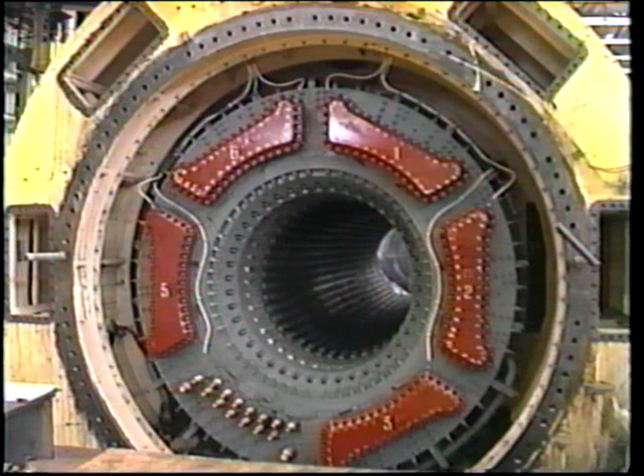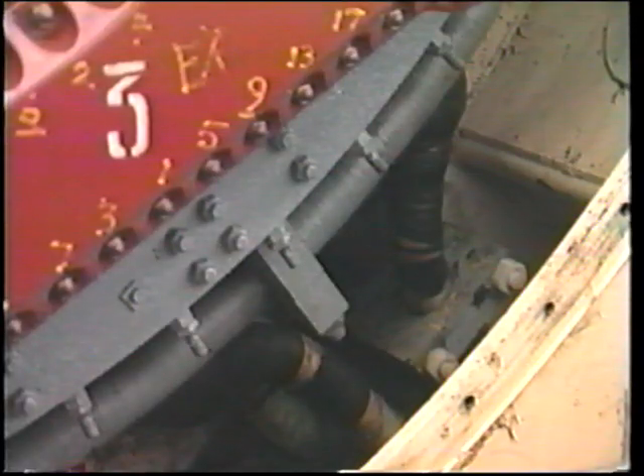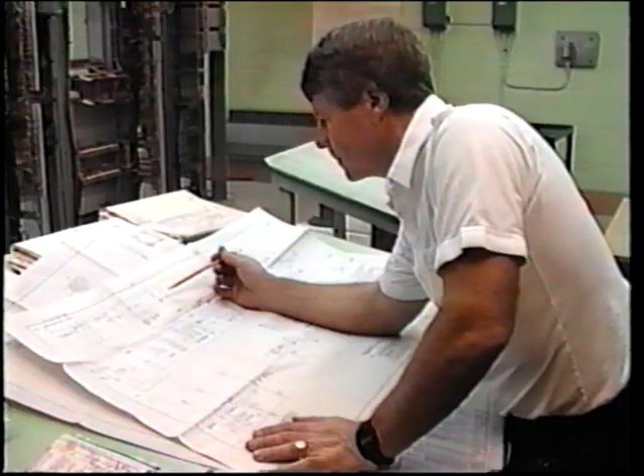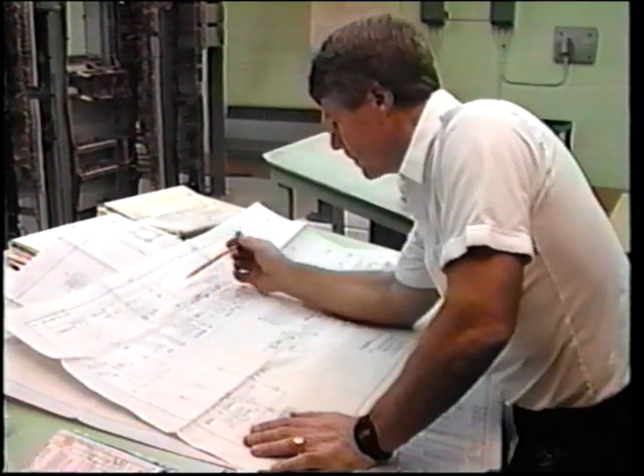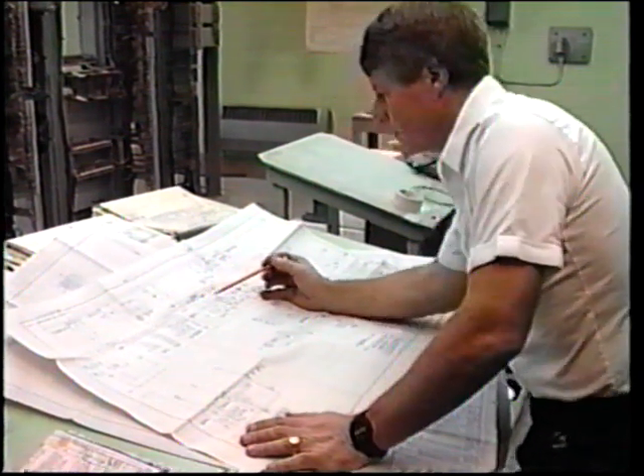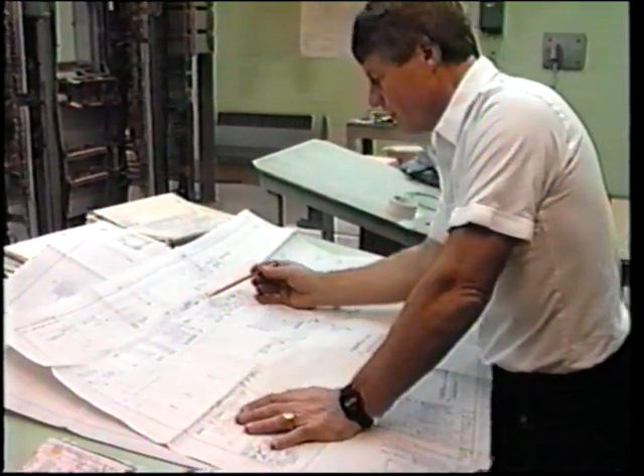During the modifications, the generator CTs had been removed so as to allow changes to be made to the generator support structure. The investigation showed that upon reinstallation, the B phase line side CT was wired backwards. The drawings and markings were correct, but the electrician made a mistake when connecting up. As in the previous cases, this shows how vitally important it is that all wiring be thoroughly checked after any modifications or installation work has taken place. Perhaps the unit was required back online in a hurry. Does that sound familiar to you?